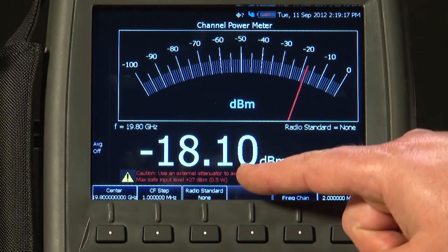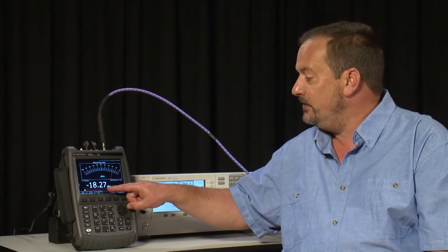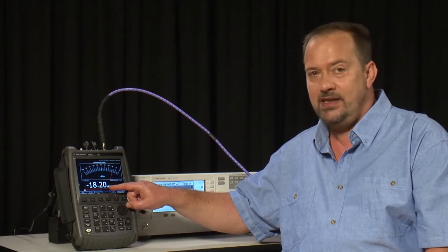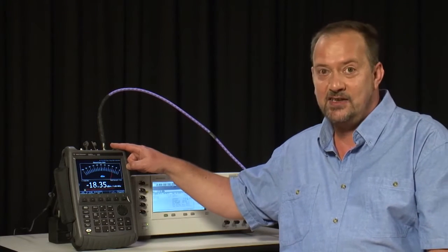There is a red warning on the screen here, which is just a little reminder that if you are connecting directly to a transmitter, you really ought to think about also inserting an external signal attenuator.